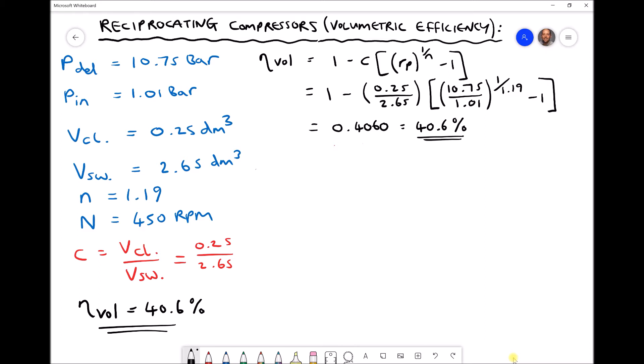On the screen we have the formula that was used in order to determine our volumetric efficiency, and we used the values for pressures and volumes as shown on the left hand side. We found using that method that our volumetric efficiency came out to be 40.6%. However, there is an alternative way to determine volumetric efficiency, and the alternative formula is induced volume — written as V_in — divided by swept volume.